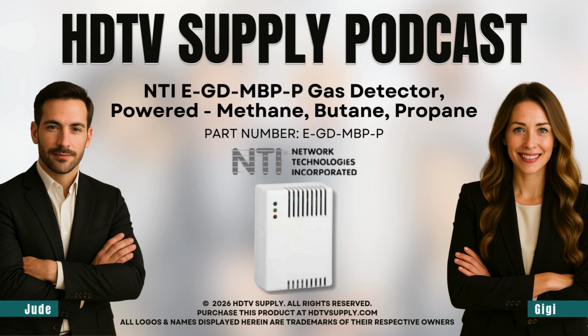Okay, level 1 is the high sensitivity setting. For methane, it trips when concentrations go over just 0.5%. Just 0.5%? 0.5%. And for propane and isobutane, that threshold is even lower, down at 0.3%. And just for context, the industry standard lower explosive limit for methane is what, around 5%? It is. So this level 1 setting is designed to catch a leak long before it becomes a measurable threat. It's a very, very early warning system.